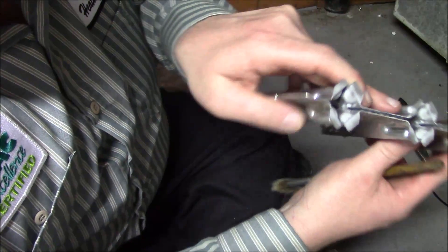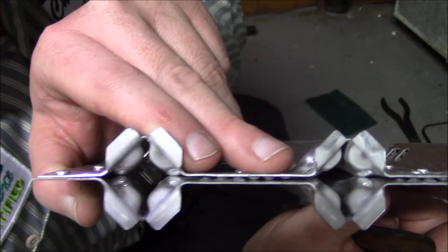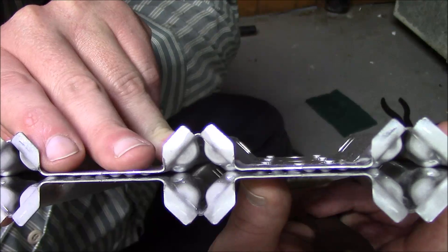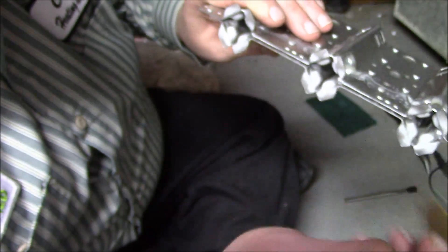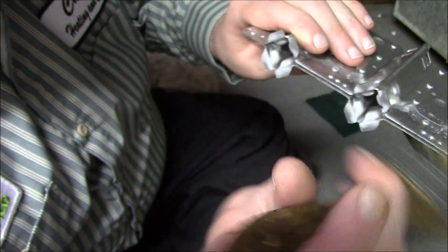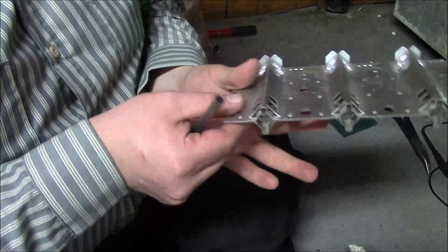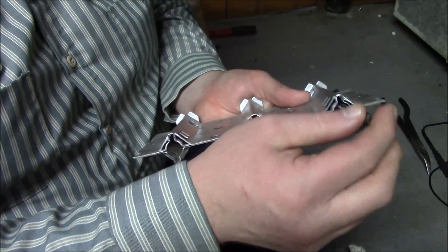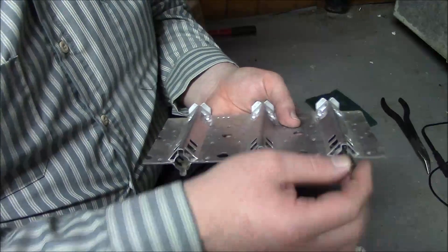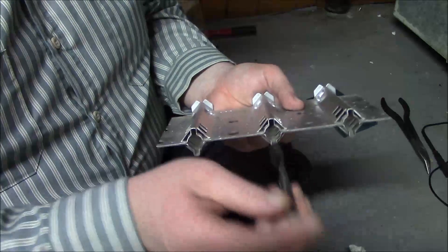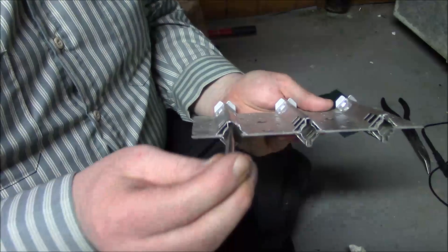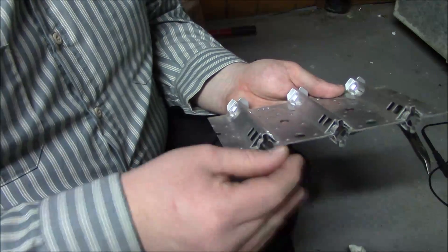Now when we look at this bad boy here, you see that gap in between with those little bumps - those are your crossovers, very important. Just go like this, brush it out a little bit. Each time you do that you'll see a whole bunch of dust come out. Take a burner, take your flux brush like this, and in and out. Put the brush in the hole and you go in and out like this, kind of rotate a little bit.